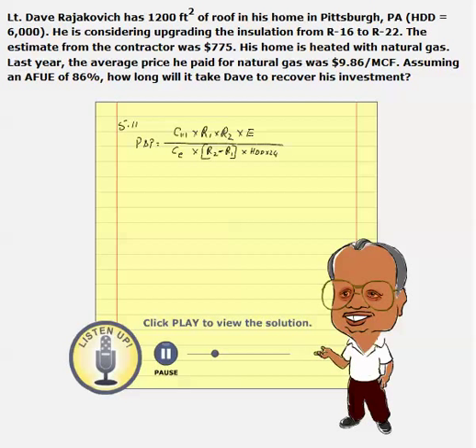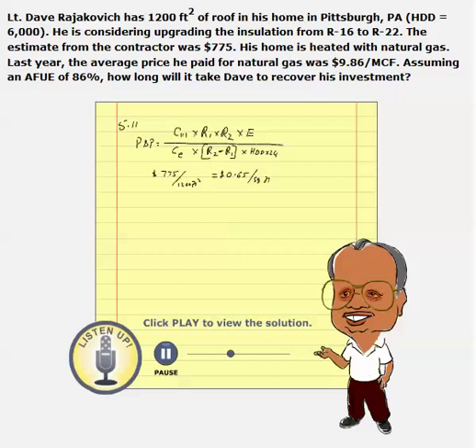Do we have all the pieces of information for this formula? Cost of insulation should be in dollars per square foot. Dave has got an estimate of $775 to cover a roof area of 1,200 square feet. To cover this area with insulation it costs $775, so the cost per square foot is 65 cents per square foot.